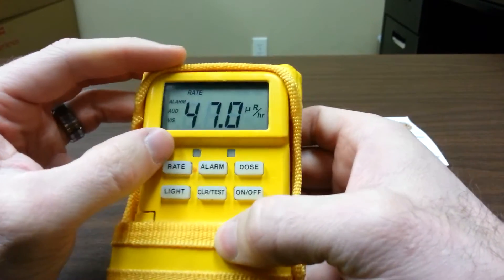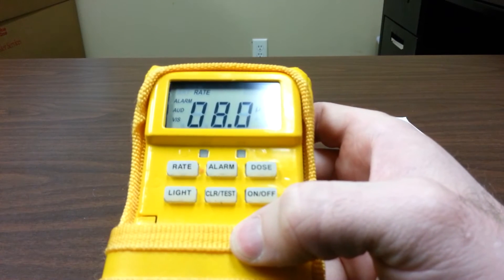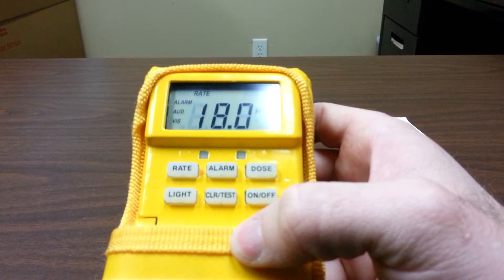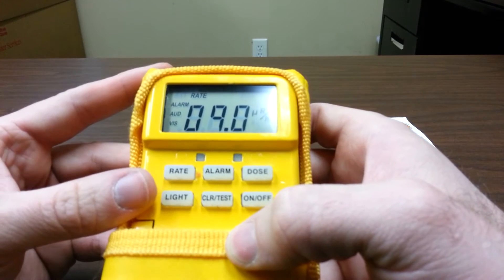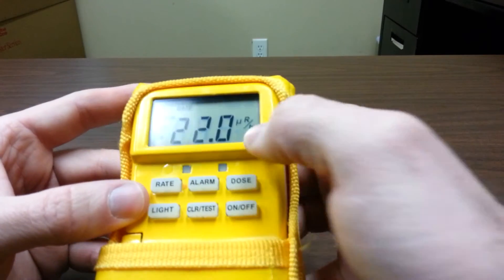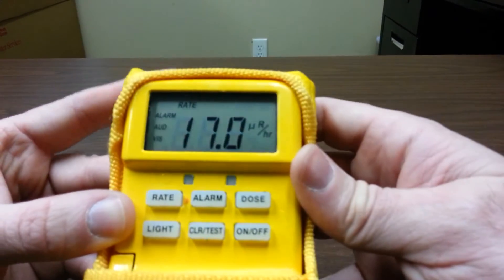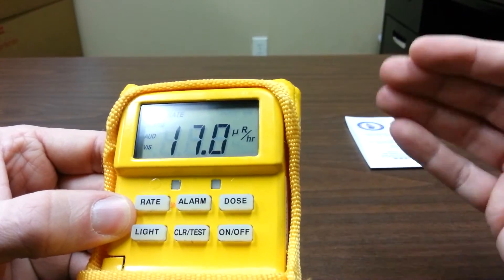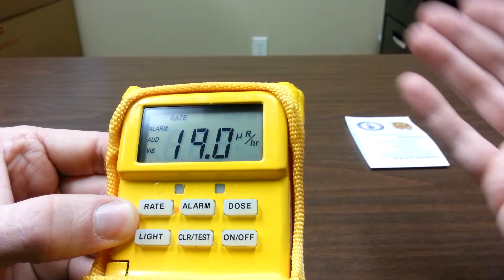So we're going to turn it on. It'll go through a brief warm-up and start providing you a dose rate. This rate is, in essence, your speedometer — it can go up and down based on the presence of radiation. You should always get a reading; there's enough natural radioactivity on Earth to produce a reading in the low numbers. We're using the µR scale here — it's an auto-adjustment scale. It'll start in the µR, go up to the mR, and up to the R in the most extreme cases. These are both 100-factor differences.